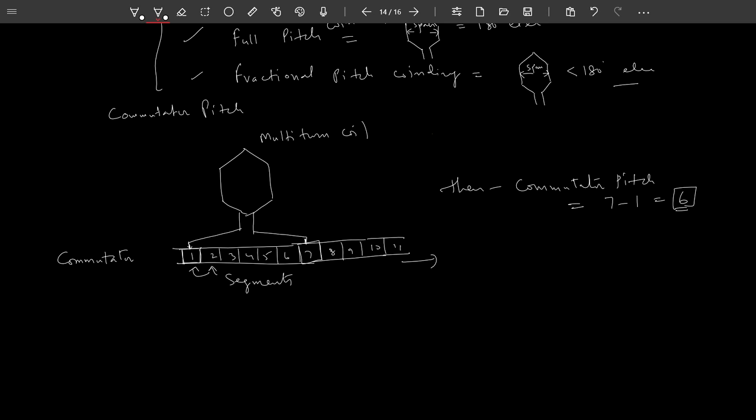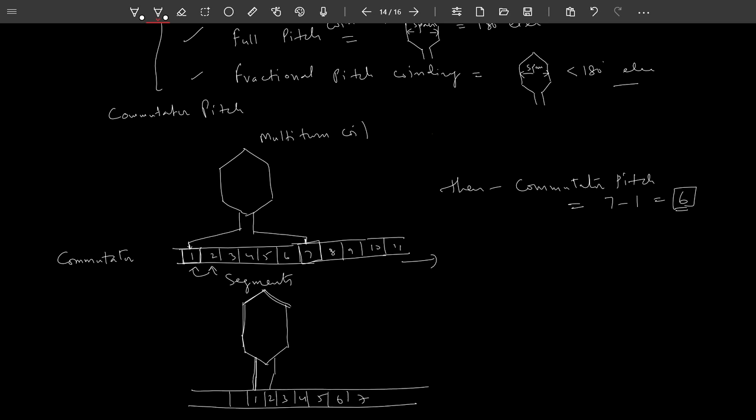In some cases, windings or coils may be connected to side-by-side commutator segments. For example: 1, 2, 3, 4, 5, 6, 7. The starting coil side is connected to segment 1, and the end of the coil is connected to the next segment 2. In this case, the commutator pitch is 2 minus 1, which equals 1. Normally the commutator pitch is denoted by yc.